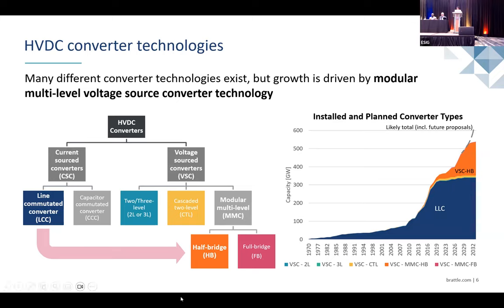You also see the trend that before 2020, a lot of projects were based on LCC converters. The main purpose of these converters is to transmit power over a long distance between grids. But as I said before, the trend has changed nowadays. There is a lot of renewable power that you want to integrate into the grid. LCC is not really compatible with renewable generation, and therefore you see VSC coming into play. Most of the time, VSC is being used by the clients.